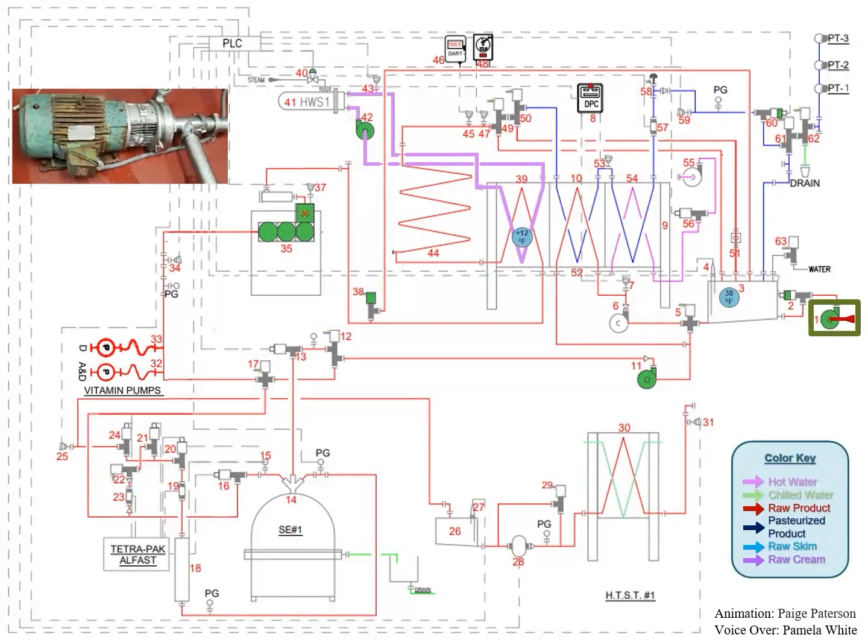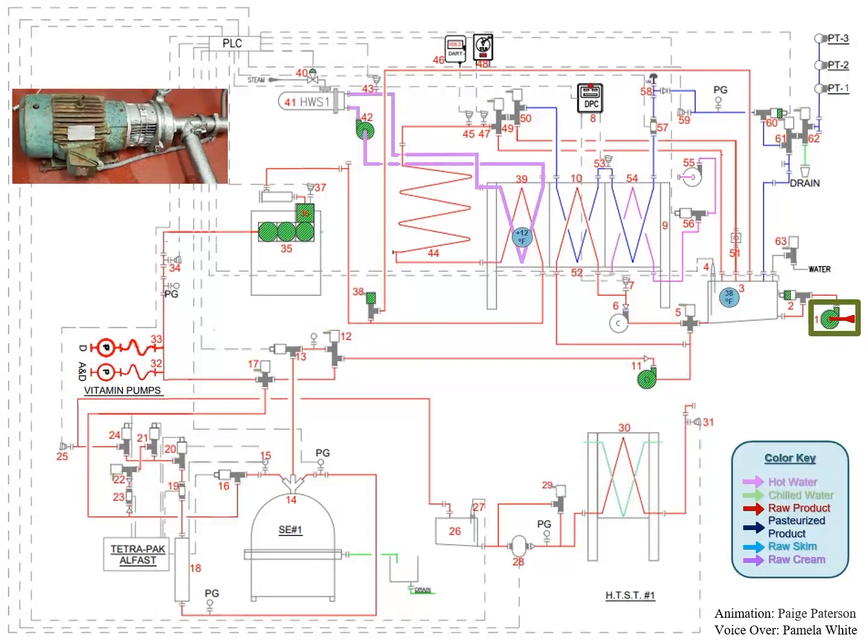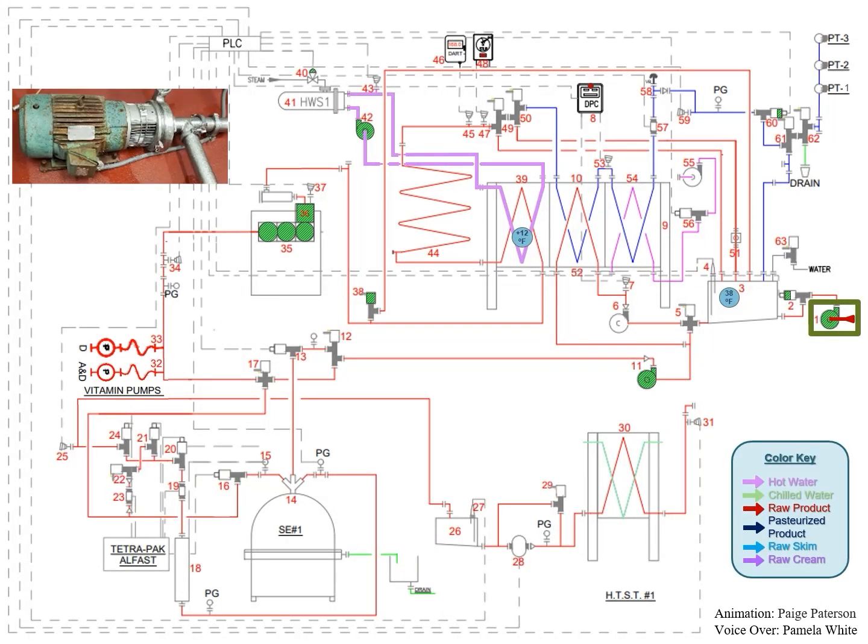The raw supply pump is designed to supply the balanced tank with 100 gallons per minute when the HTST is producing 3.25% milk and 110 gallons per minute when producing skim milk, when the raw silo is near empty and the suction head pressure at the inlet of the raw supply pump is very low.